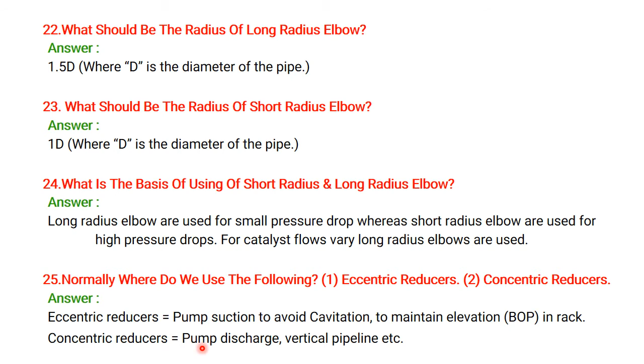No. Here, pockets may form if a concentric reducer is used at pump suction, which results in cavitation and causes damage to the pump. To avoid this problem, an eccentric reducer with flat side up, FSU, is used at pump suction. Where are ERW, electrical resistance welding, spiral and longitudinal pipes used?